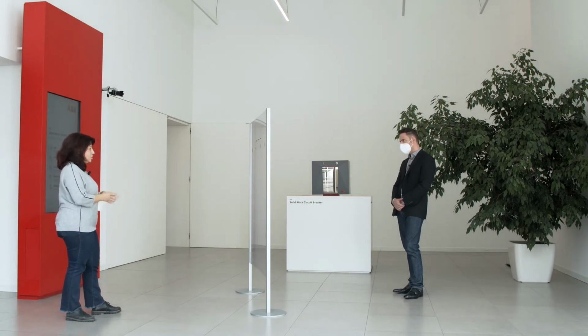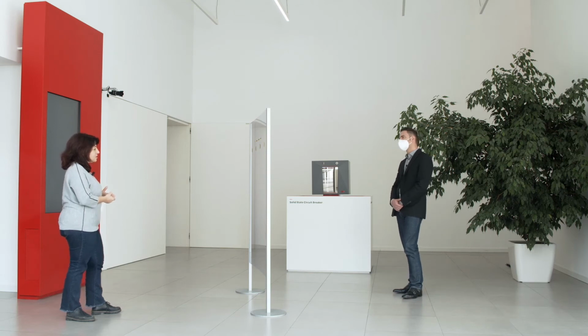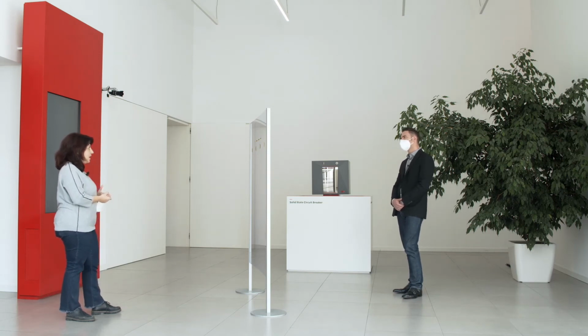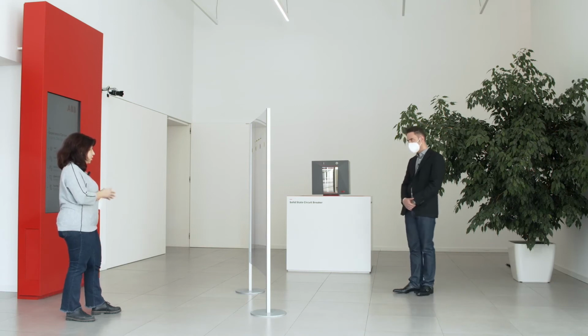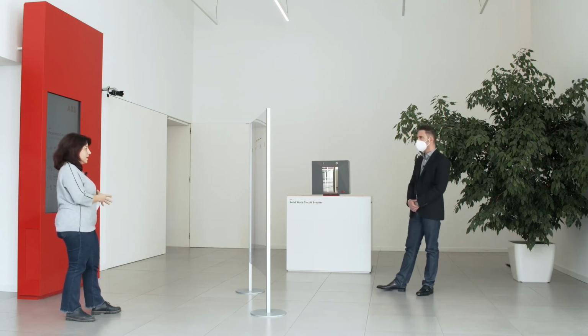The situation is different for sodium sulfur battery that, as you know, is realized in only one configuration and size. The internal ohmic resistance of the cell is around 3 milliohm, and its value is very strongly dependent on the internal operating temperature of the battery, of the module.